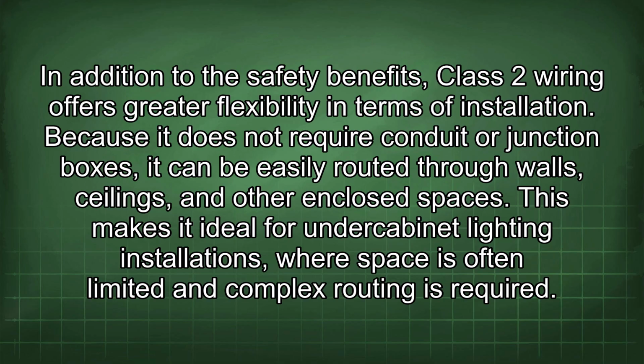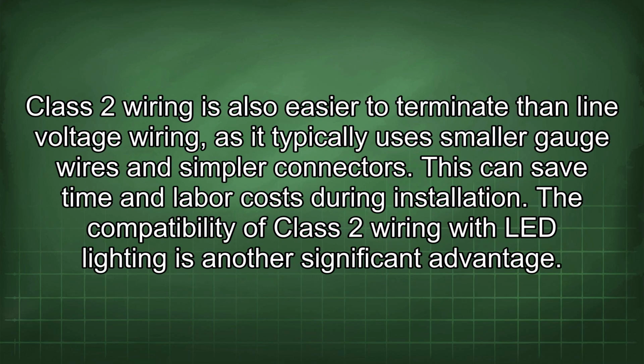In addition to the safety benefits, Class 2 wiring offers greater flexibility in terms of installation. Because it does not require conduit or junction boxes, it can be easily routed through walls, ceilings, and other enclosed spaces. This makes it ideal for under-cabinet lighting installations, where space is often limited and complex routing is required. Class 2 wiring is also easier to terminate than line voltage wiring, as it typically uses smaller gauge wires and simpler connectors. This can save time and labor costs during installation.